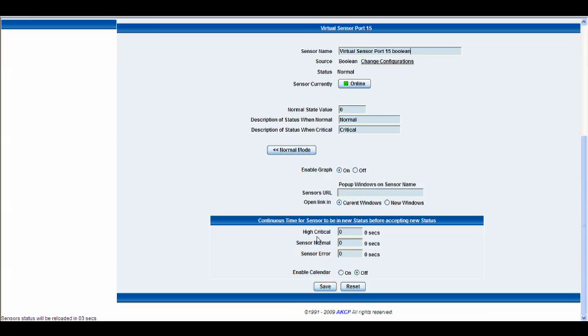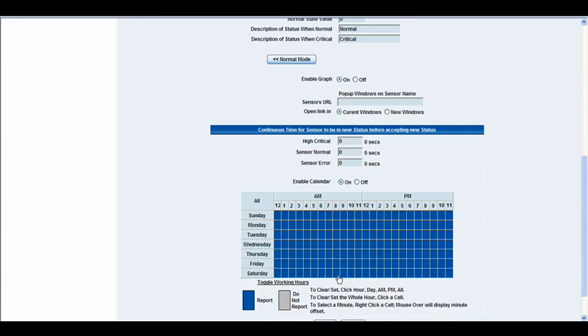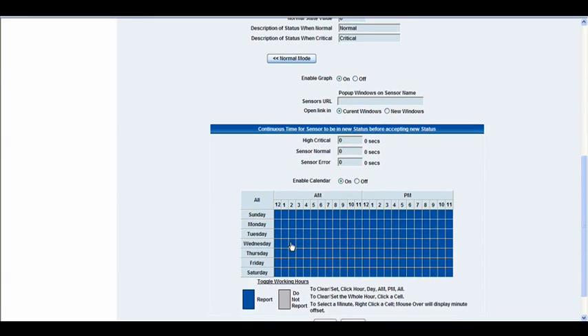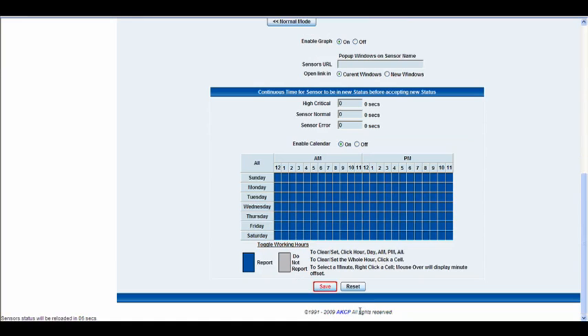For example, if you want the high critical to remain in a high critical status for let's say 10 seconds before it reports on that status, that's what you'd write in that box. Then finally at the bottom we have our calendar options. You can toggle that on or off, select the days of the week and the hours of the day in which you'd like this sensor to report. We'll go ahead and click save.